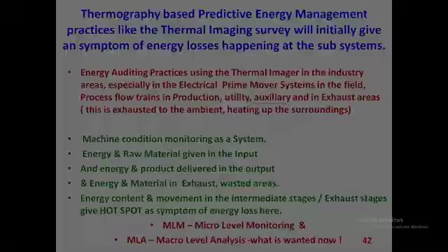This is what is seen through infrared thermal imaging. What is the temperature of the motor at the 3, 6, 9 and 12 positions? Between 3 and 9, it should be less than 20 degrees, or between 6 and 12, it should be less than 20 degrees, and driven to non-driven, it should be less than 20 degrees.